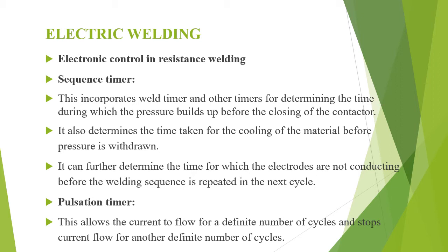Sequence timer. This incorporates weld timer and other timers to determine the time during which the pressure builds up before the closing of the contactor. This is known as squeeze time. It also determines the time taken for the cooling of the material before the pressure is withdrawn. This is known as hold time. Also, it can further determine the time for which the electrodes are not conducting before the welding sequence is repeated in the next cycle. This is known as off time.